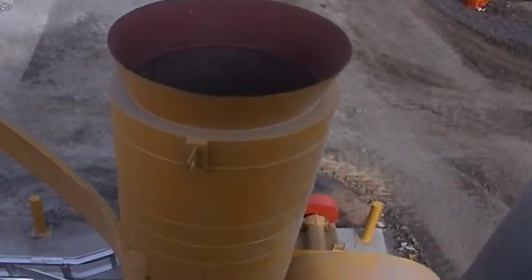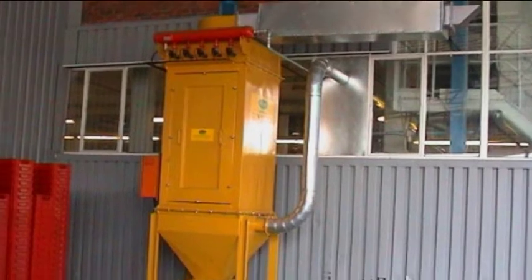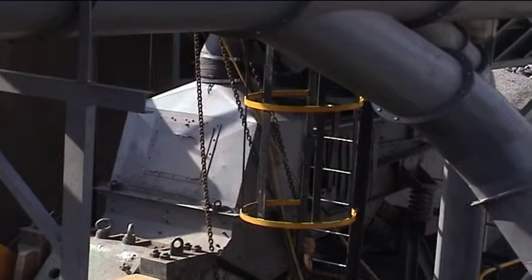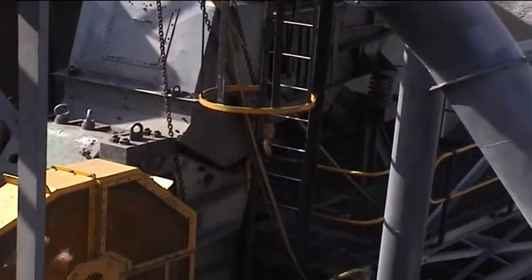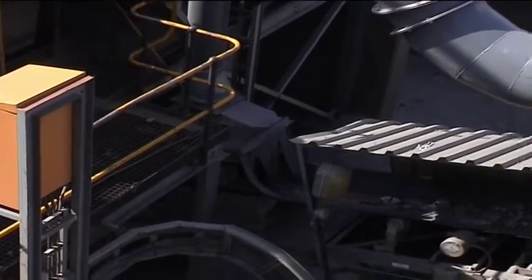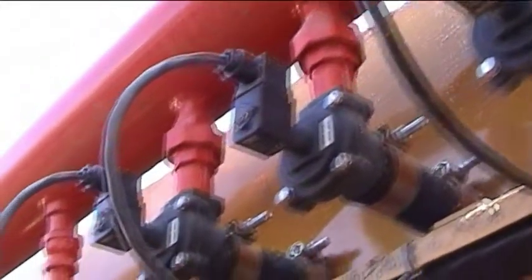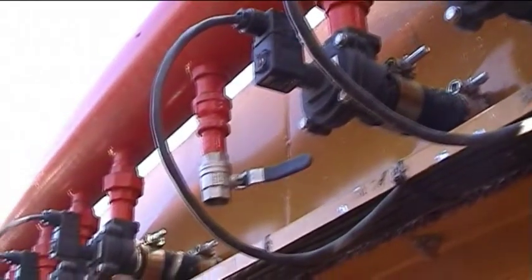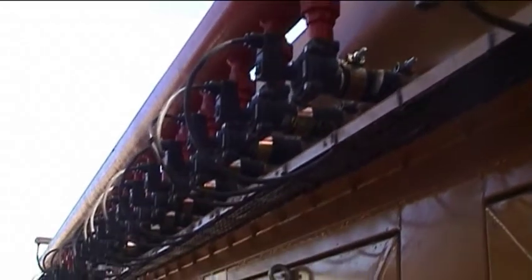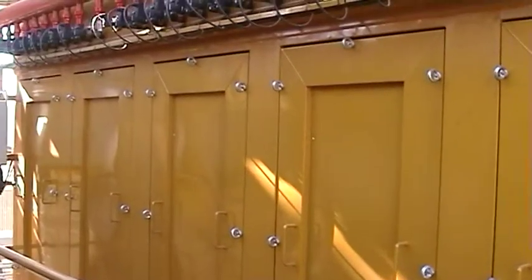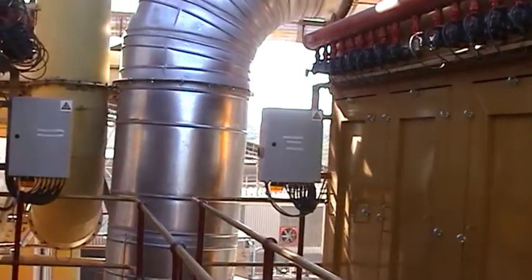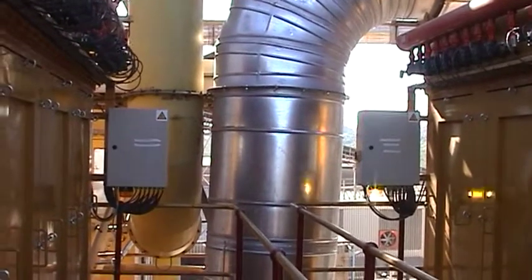The dust collector range offers automatic, continuous online filter cleaning, thereby maintaining a low, even pressure differential under normal working conditions. The filter cleaning makes use of compressed air, which is delivered to a series of pulse valves via a common compressed air manifold. The pulse valves, which are coupled to an electronic controller, deliver a sequential cleaning cycle which actuates each pulse valve under a preset program or via differential pressure monitor.